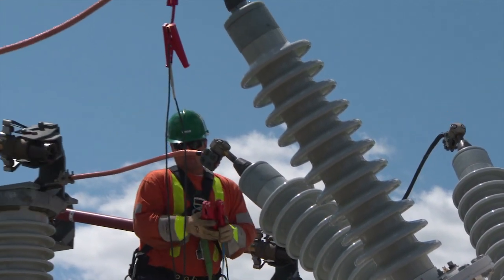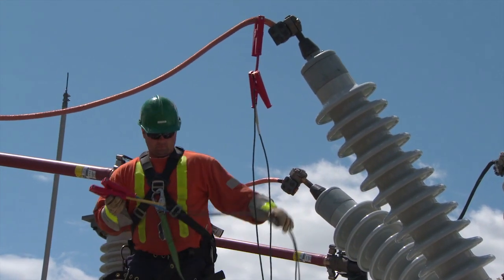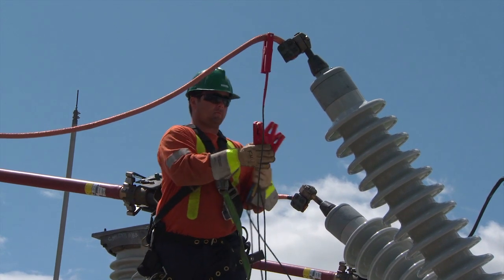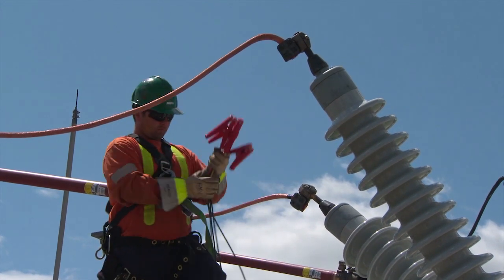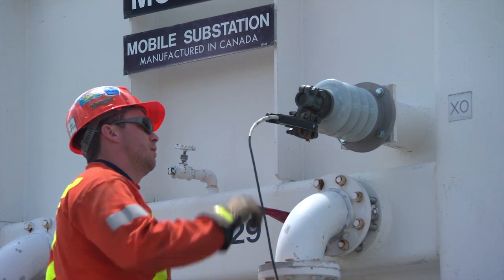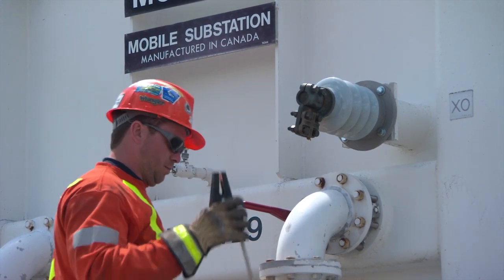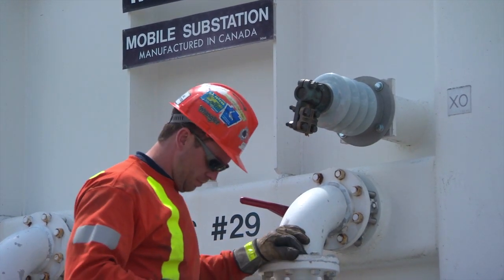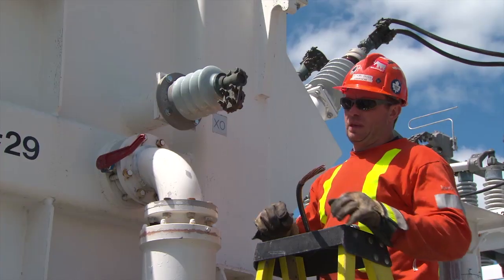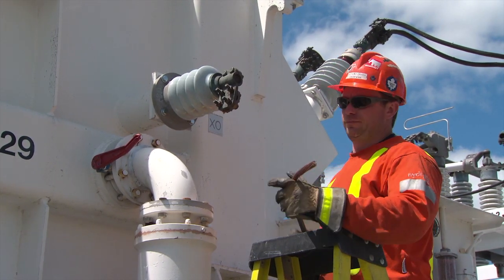After the ratio test is complete, remove the high voltage ratiometer leads from all 3 bushings and remove the low voltage ratiometer leads, including the XO lead. The XO lead must be reconnected to the XO bushing after all diagnostic testing on the MUS has been completed.